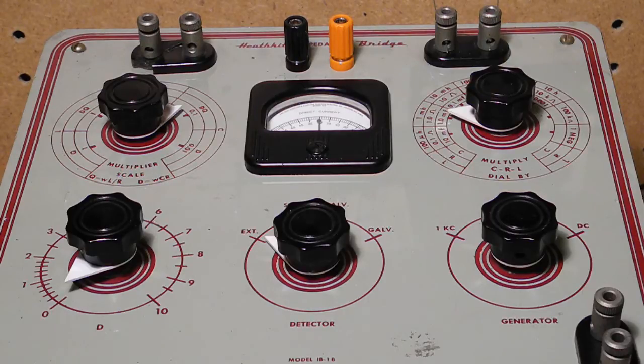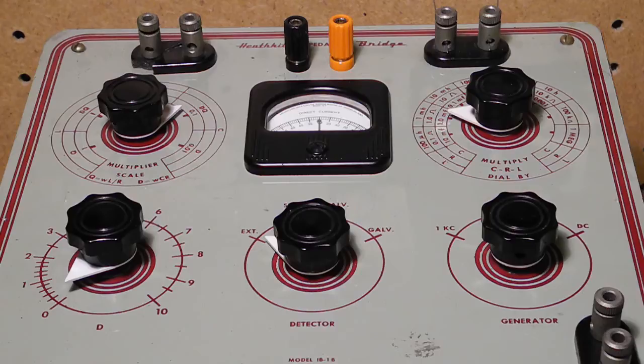Resistance measurements use a Wheatstone bridge circuit. Inductance and capacitance measurements can use either Maxwell or Hay bridge circuits. The Maxwell bridge is used for devices with low Q factor, and the Hay circuit is suitable for high Q devices. The internal circuitry uses all passive components with no tubes or transistors. The unit weighs about 9.5 pounds.